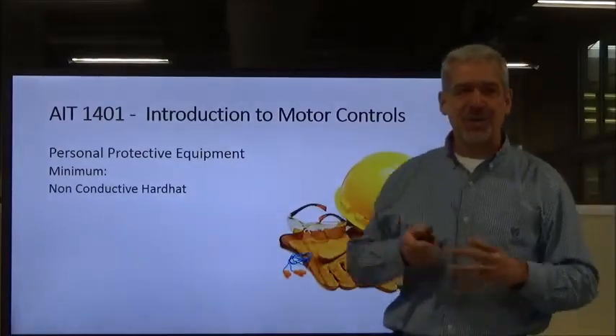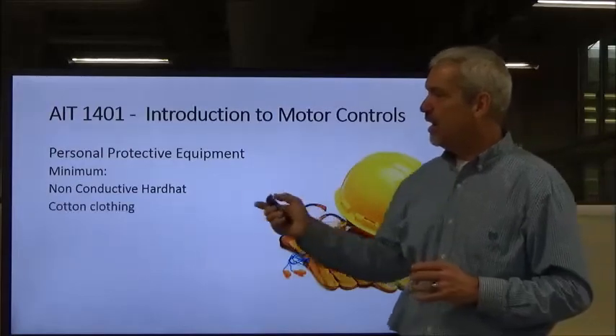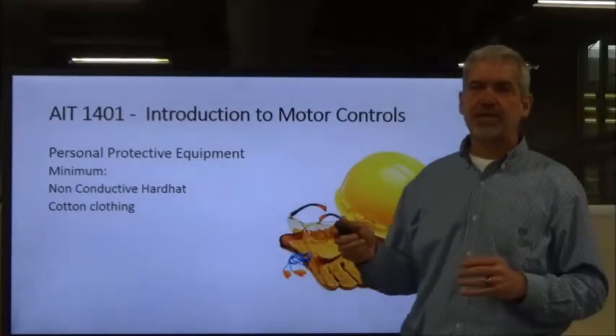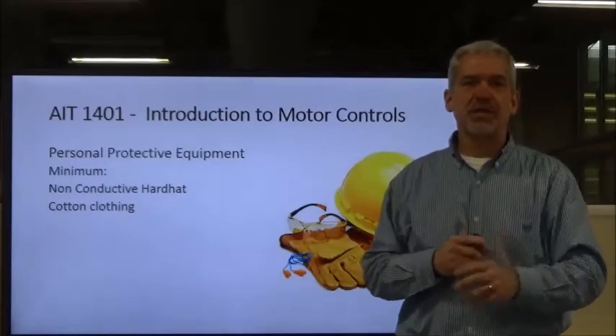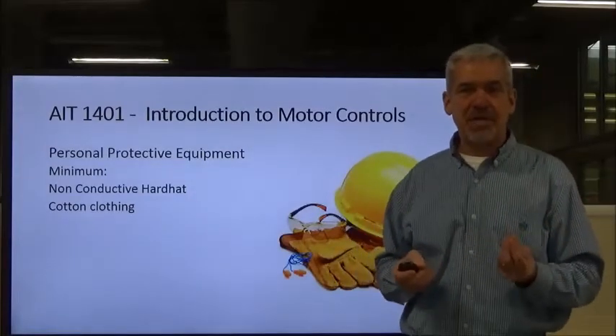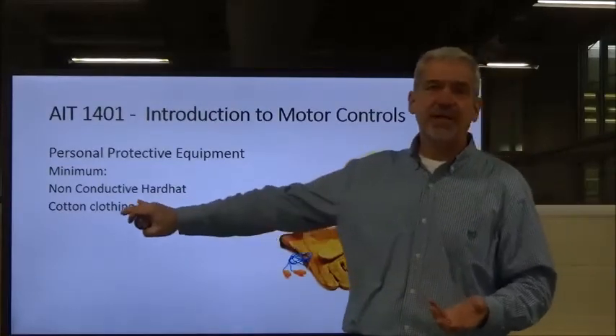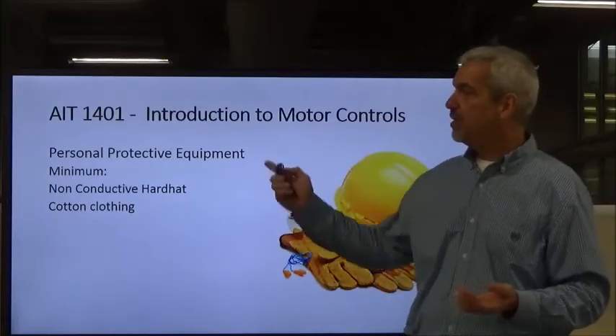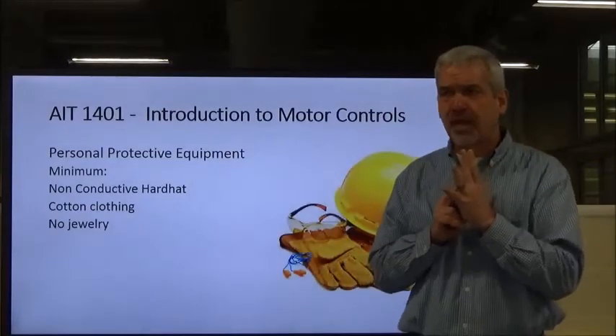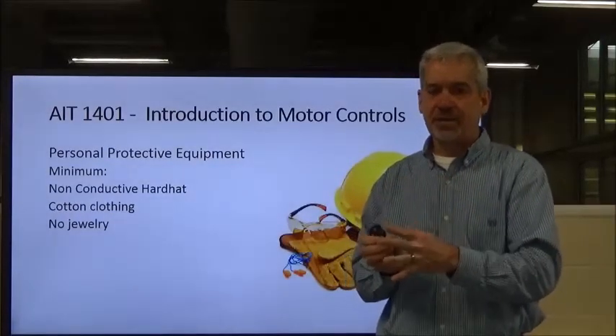As a minimum, you need a non-conductive hard hat. Back in the day, construction workers wore metal hard hats, which are conductive — that's not smart. You also want to wear cotton clothing. Materials with rayon, polyester, or other man-made materials become very hot and melt, actually melting into your skin, even when woven into cotton. Cotton is the best protective clothing when dealing with electrical equipment. No jewelry — jewelry is a conductor, and you can get close to a live conductor and bump it without realizing it.